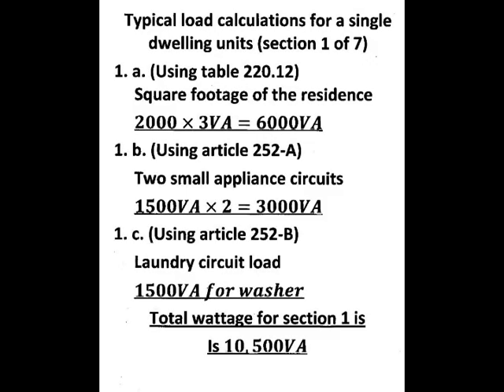Using a typical house, we're going to say that it's 2,000 square feet. Using table 220.12, you take the square footage of the residence and multiply it by 3 volt amps. That gives you 6,000 volt amps. You've got to have the two small appliance circuits added in there, which is 252-A, giving you 3,000 volt amps. We also include the laundry circuit 252-B, which is considered 1,500 volt amps for your washer. That gives you a total wattage of 10,500 volt amps or watts.